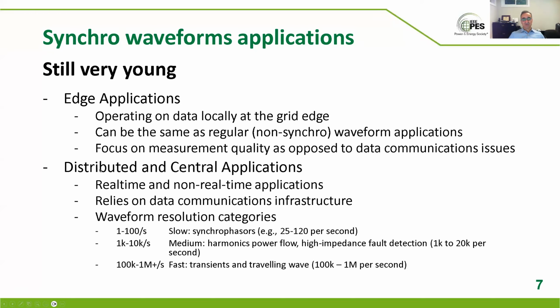Most of the interesting things come when you're talking about more than one measurement system at different locations, so that time synchronization and time tagging can help you coordinate or correlate the waveforms and get some useful information: phase, power flow, traveling wave, if you have a type of synchro waveform with the right bandwidth and the right speed. But I would call these distributed or central applications, meaning there is not just measurement, but often some level of communication needed to get the data to another place or many other places. And these could be real-time applications or non-real-time applications, again getting data from multiple places.